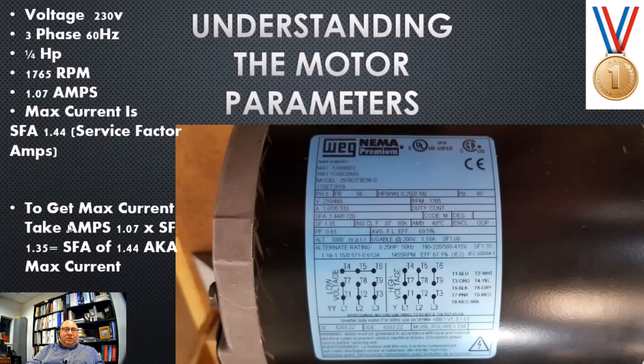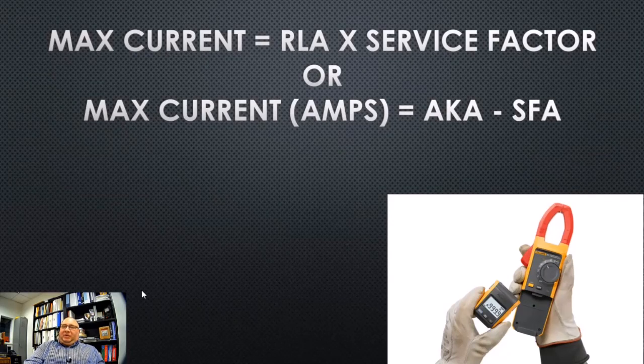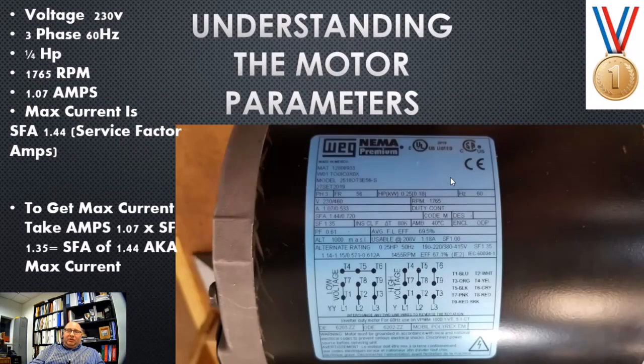All right, and this will go into how to get your service factor amps. It's basically, we're looking for the max current this motor can run at so we can program it into the drive. We'll just do it one more time because a lot of people have a little trouble with it. This is not locked rotor, but let's call this running load amps or full load amps. Under normal operating conditions, we would take the amperage on the nameplate and times it by the service factor. Remember, most motors are 1.15. This is 1.35. And that's going to give us our max current amps, also known as service factor amps. And like I said, the good thing is this motor here has the service factor amps already built into the nameplate. If it did not have that, then you're going to have to take your amperage here and times it by your service factor right there.